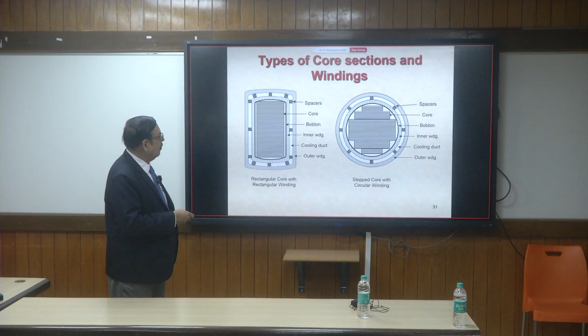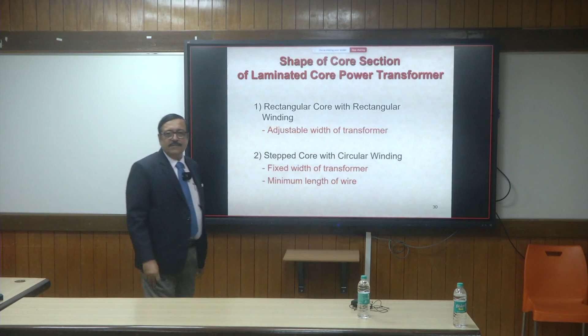What are the advantages and disadvantages? A rectangular core with rectangular winding gives you the adjustable width of the transformer. Suppose you tell me I have to fit the transformer within this only, for a particular kVA. I can reduce the width, make it longer this way and make it fit into my equipment. But if I choose a circular core, I don't have that change. A radius on either side is the radius. I can't change the dimension. I can't make it fit there unless I reduce the size. So fitting sometimes becomes the important factor in equipment.